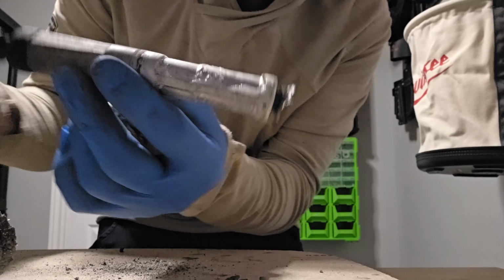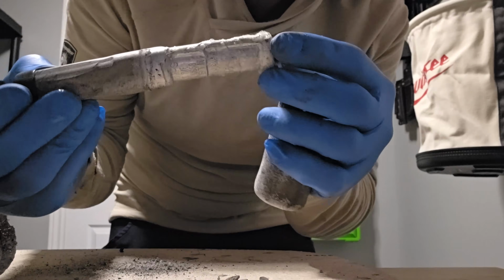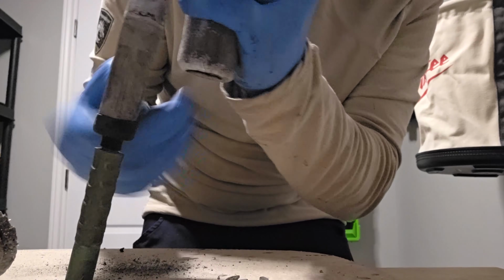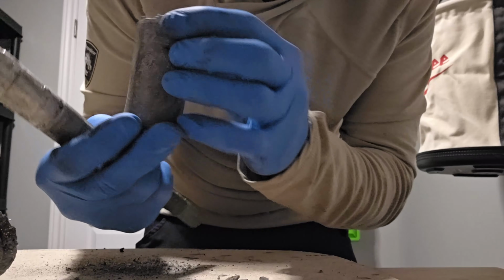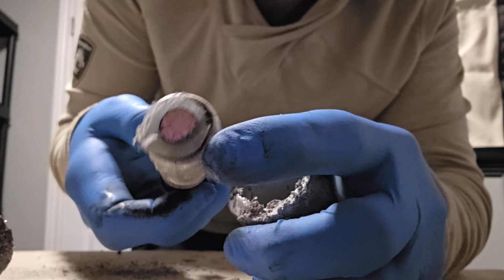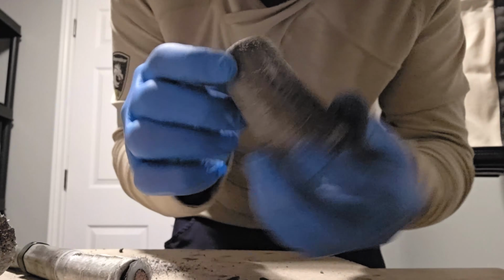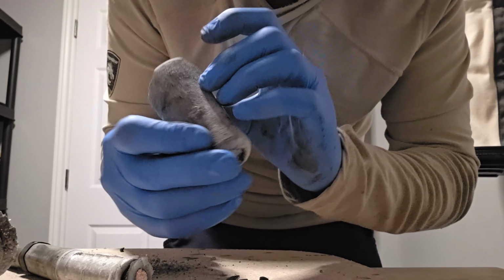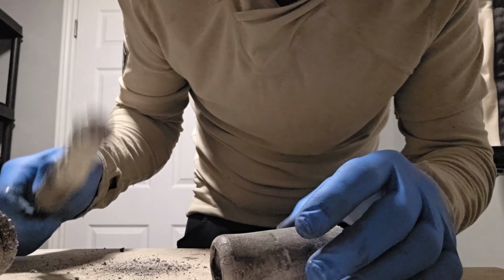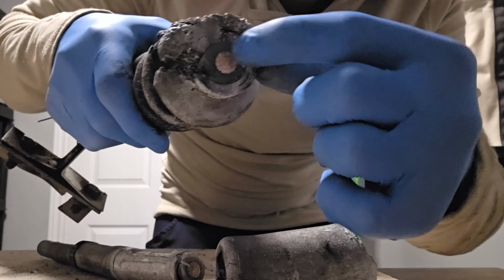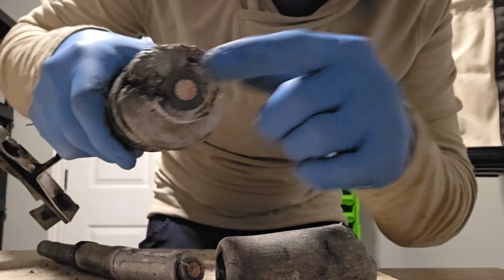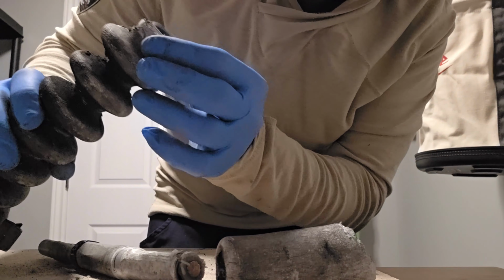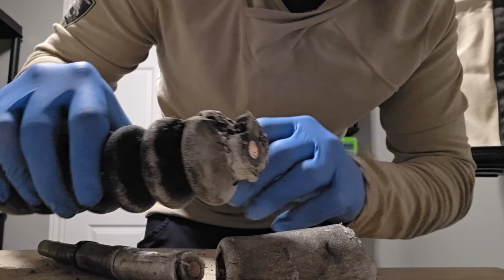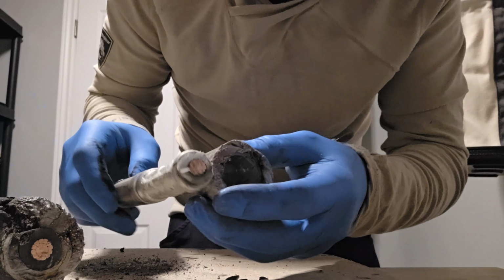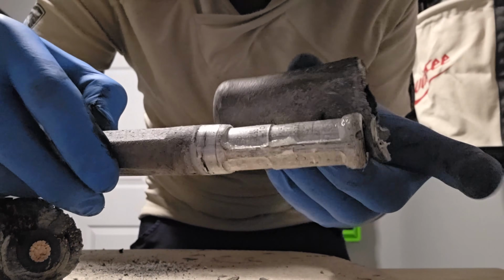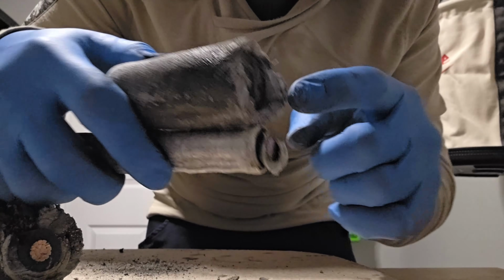So this is the stinger that crimps onto the cable. Interestingly enough, there's no damage to the insulation there either. So I would say, by the looks of things, the insulation on the cable itself didn't fail at any point. So it doesn't look like a situation where it was water damage. Maybe there could have been water in the cone itself. But that lined up, you can see the mark here where that was covering, and the failure point was right at the bottom.